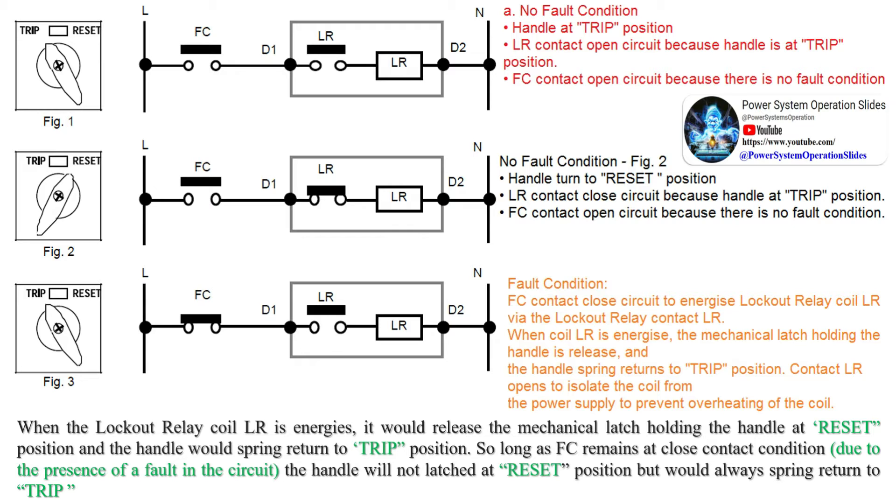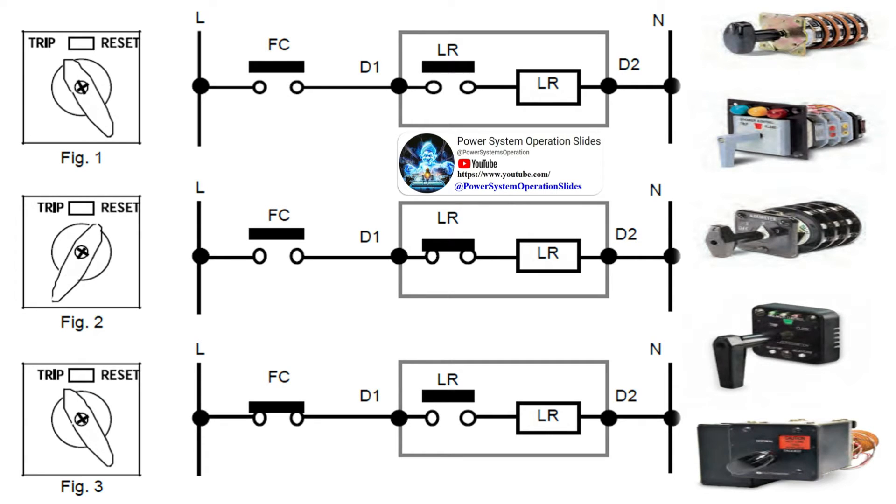The principle of a lockout relay: a relay is a protection device which senses an abnormal condition or fault in the system and issues a tripping command to the circuit breaker to isolate the faulty part. The decision for fault condition is taken by the relay based on its setting. If the system parameter exceeds the setting value, the relay assumes it as an abnormal fault condition. For example, suppose the current setting for an instantaneous overcurrent relay is 200% of the nominal value. If the relay senses that the circuit current exceeds this setting, it will declare it as a faulty condition and will change its output contact FC from NO to NC.